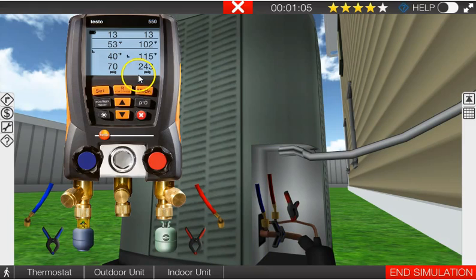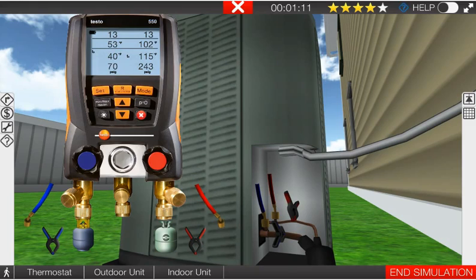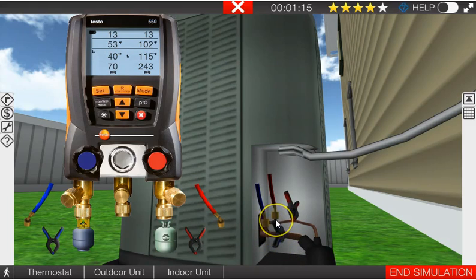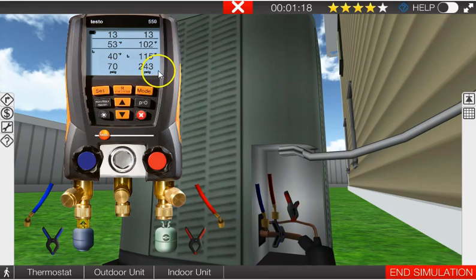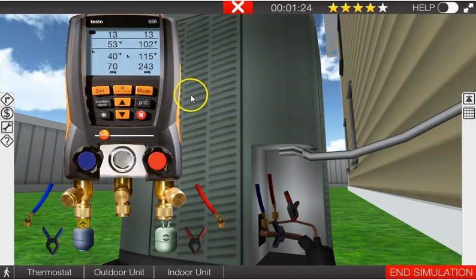So this is an R22 system. We're running 243 PSIG at the condenser and 70 PSIG at the evaporator. One thing I want you to remember: even though you're measuring the pressures right here, I want you to picture in your head when you look at this 243 PSIG that this is representative of what's happening exactly in the center of the condenser coil.